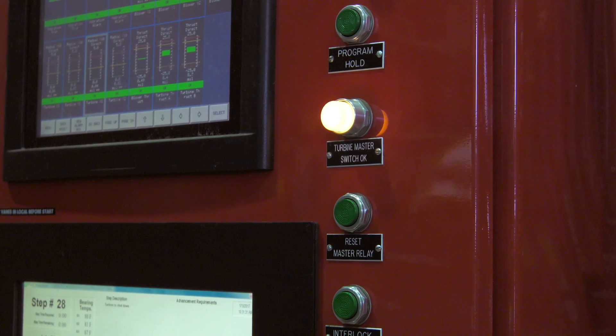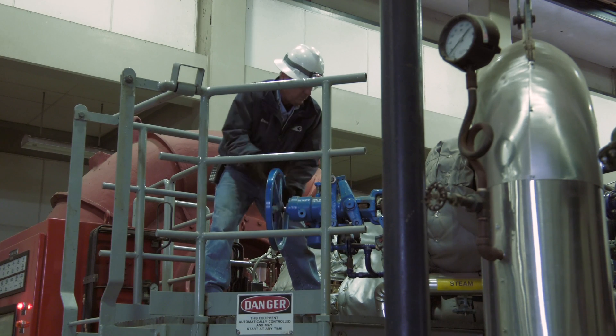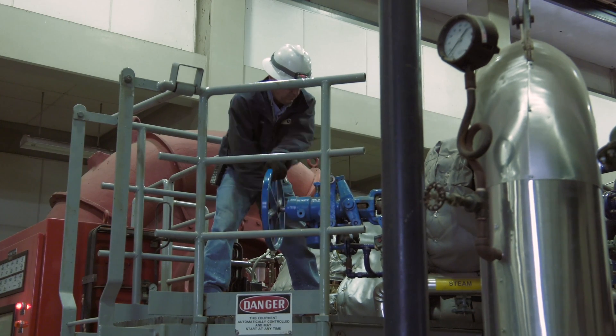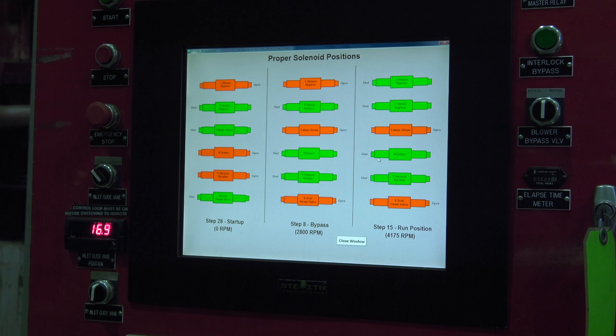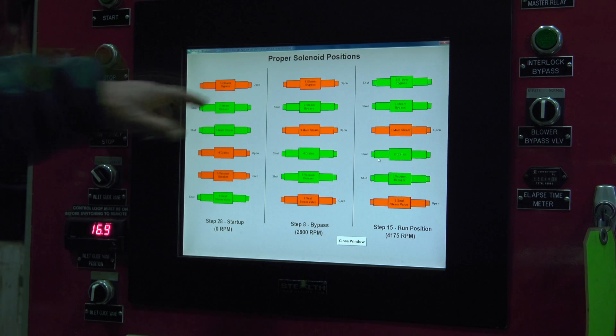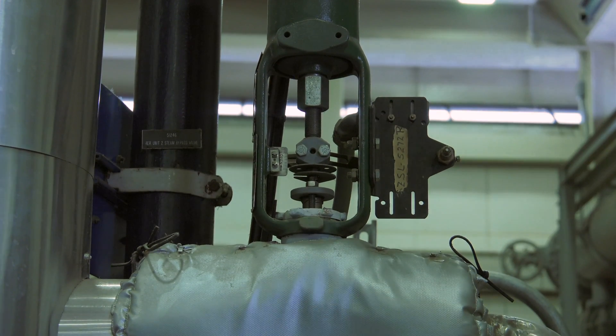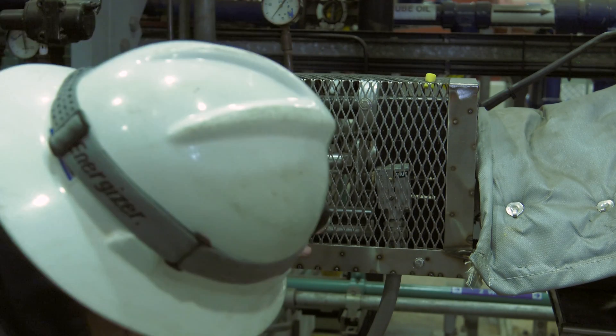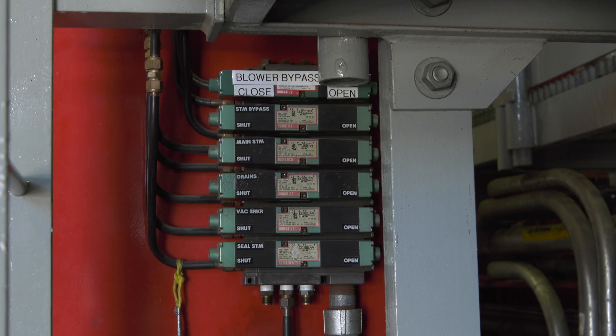Verify the turbine master switch OK light is on, then open the trip and throttle valve by slowly spinning the wheel counter clockwise. Verify the valve stays latched and the master relay OK light is lit. Check the solenoid valve positions are set properly by going to the proper solenoid position screen on the MMI. Verify each valve is in the proper position. If you need to change the position of a valve, use an ink pen or something similar to operate the solenoid and change the valve position.